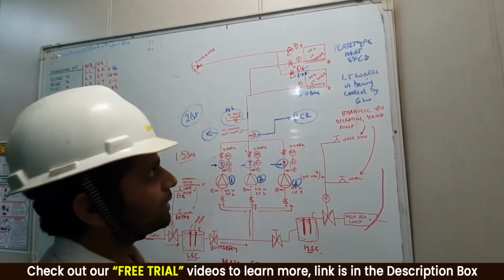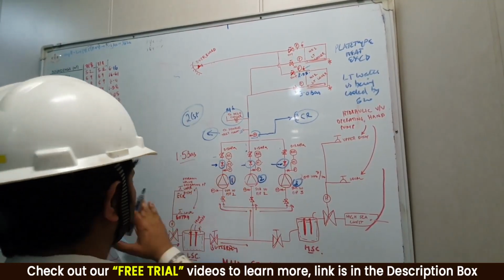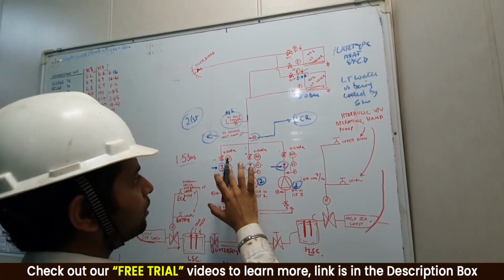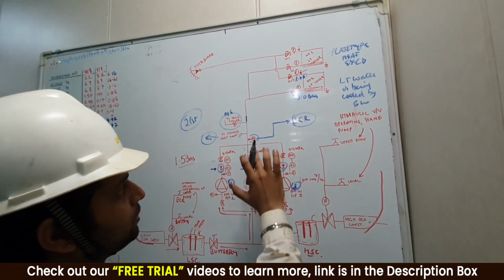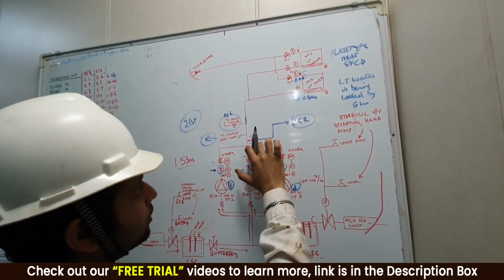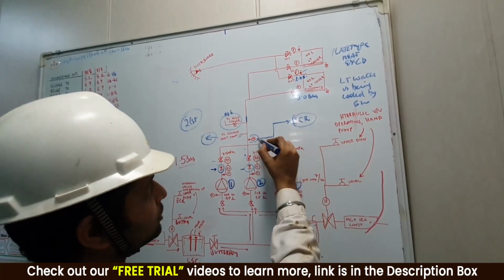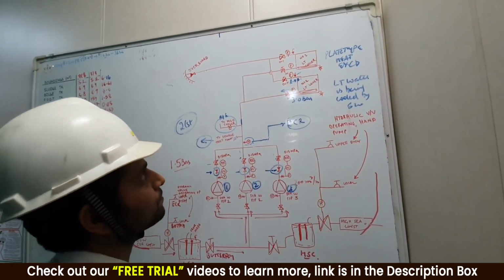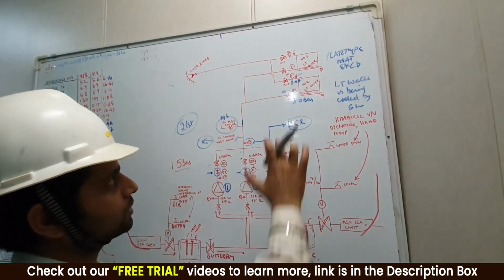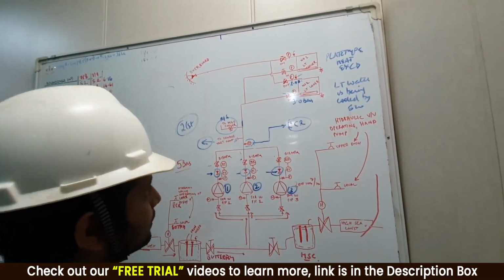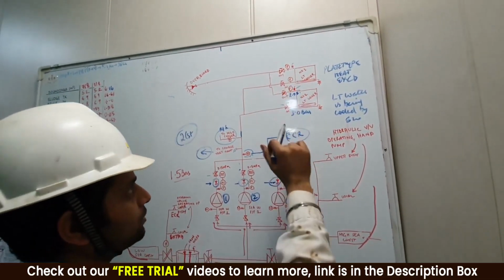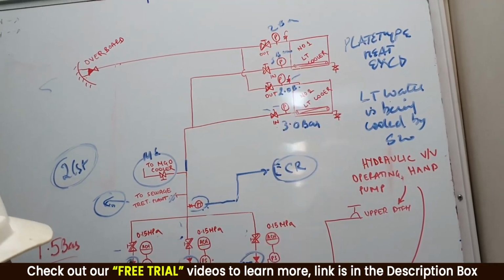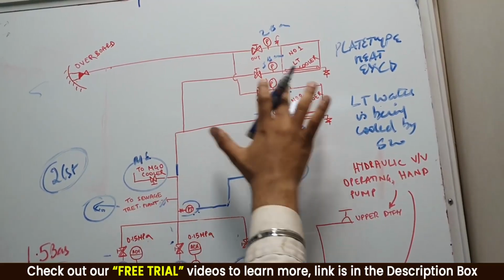Copy it. Now one day you come and see that the same system is running, the ship is at the same place, no suction pressure change, a little bit of discharge pressure change, and over here this pressure has increased. Okay, let me put it in a simpler way. You have both these LT coolers on, same 3 bar pressure over here, 2 bar pressure over here, number 1 seawater pump running and going like this.